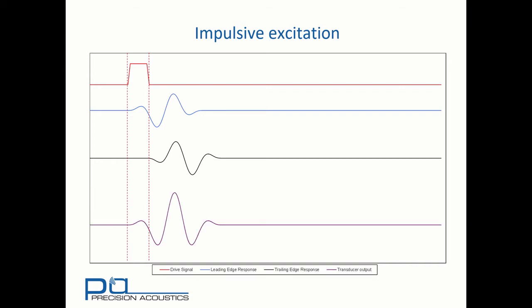Now we'll consider a square pulse. We have a copy of the transducer's impulse response from the leading edge, and a time-delayed version from the trailing edge. Notice here that because the trailing edge of the drive signal is negative going, we have a phase inverted version of the transducer's impulse response. And the transducer output is the combination of the two.